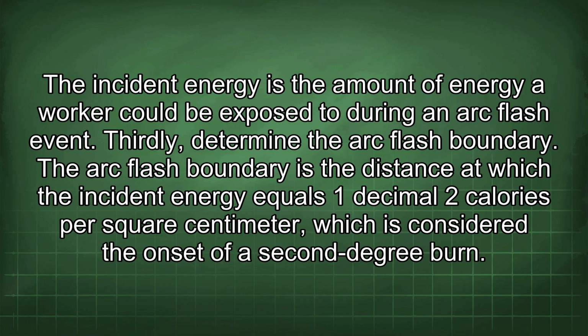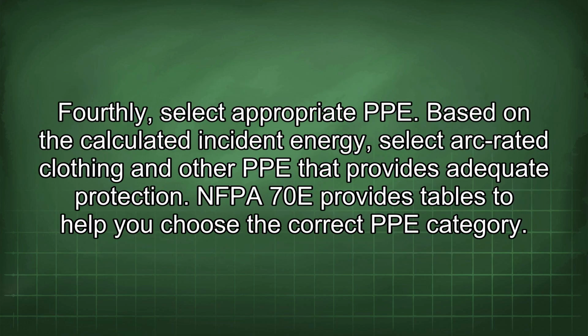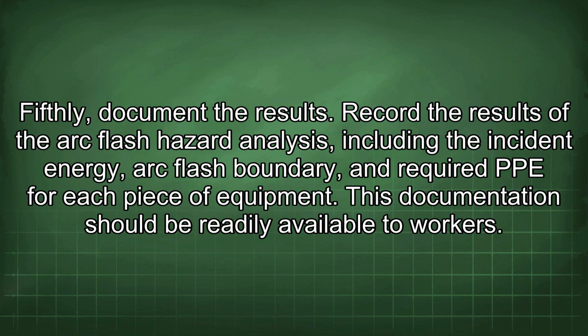Thirdly, determine the arc flash boundary. The arc flash boundary is the distance at which the incident energy equals 1.2 calories per square centimeter, which is considered the onset of a second-degree burn. Fourthly, select appropriate PPE. Based on the calculated incident energy, select arc-rated clothing and other PPE that provides adequate protection. NFPA 70E provides tables to help you choose the correct PPE category. Fifthly, document the results. Record the results of the arc flash hazard analysis, including the incident energy, arc flash boundary, and required PPE for each piece of equipment. This documentation should be readily available to workers.